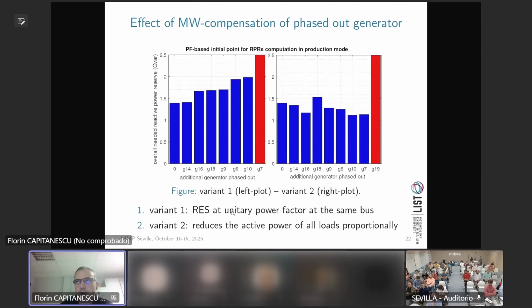So we have two variants. One is rough: we place RES at the same node at unitary power factor. In the other, we look across the system with a proportional distribution, if we don't know exactly where it could happen. You can see, for instance in production mode for RPRs, that when you disconnect G7, with variant one you already get infeasibility, but with the second variant you're able to stay feasible with G7 out—it just happens a little bit later.